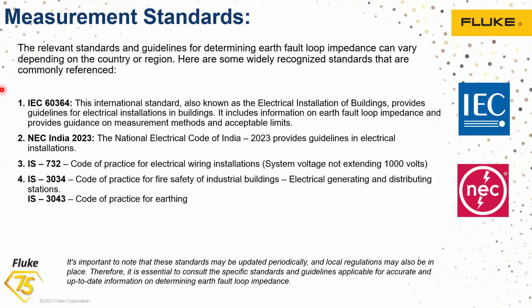Now, from the standards, IEC 60364 is an international standard. As per this standard, clear guidelines are provided about electrical installations in buildings, why it is required to do the test, and what the benefit of doing the test is. Similarly, the NEC, National Electrical Code of India 2023, had a lot of amendments, and guidelines are also provided by the NEC about the importance of testing the fault loop impedance. And from our Indian standards, of course, IS 732, IS 3034 and IS 3043. There are multiple chapters under these. Definitely all these standards recommend regularly checking the electrical installations, right?